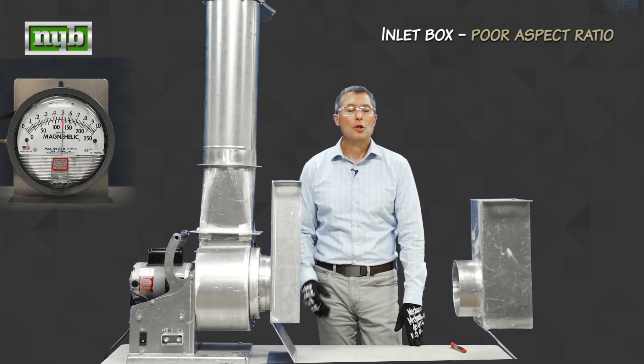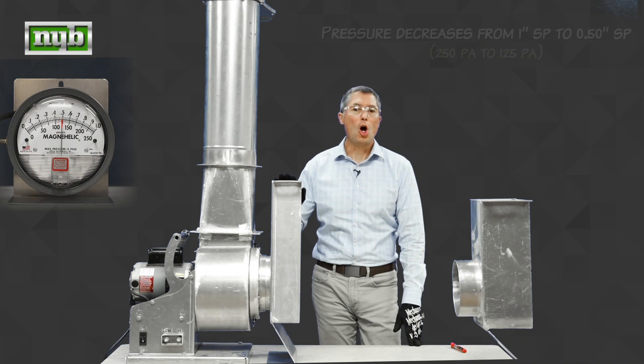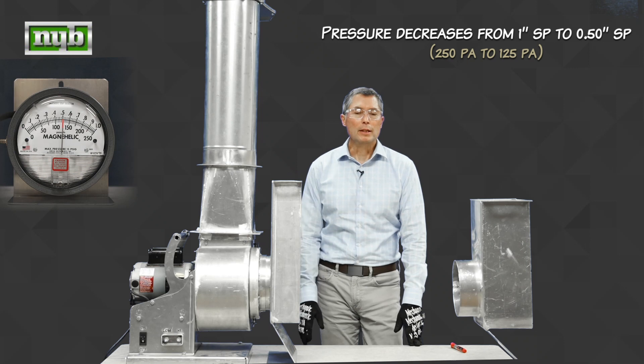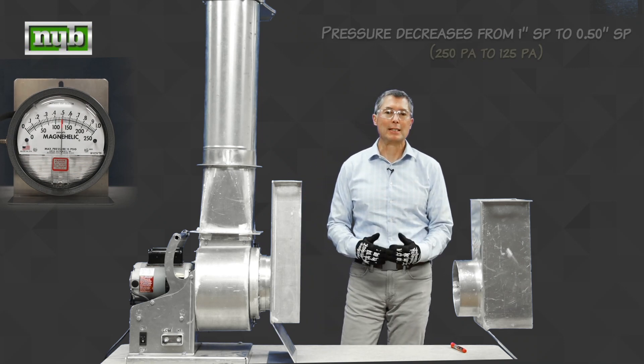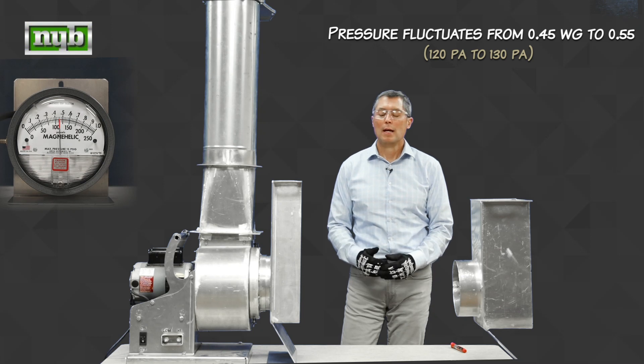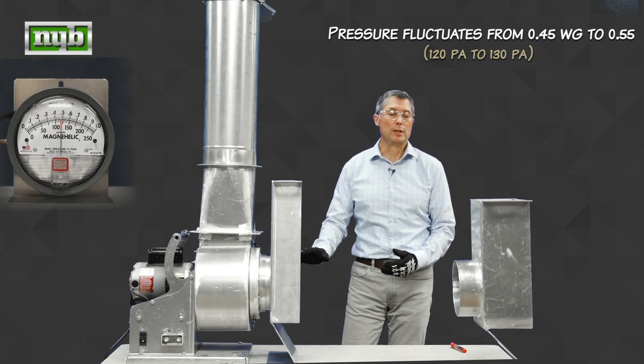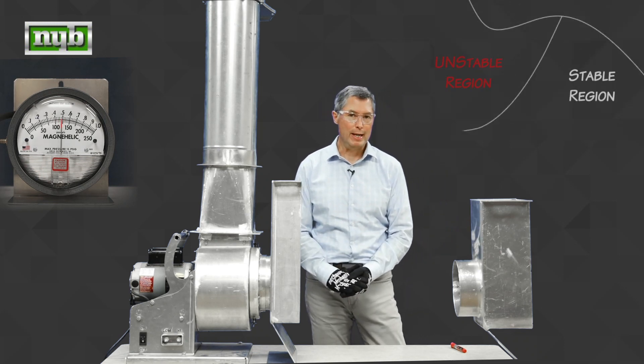Looking at the Magnehelic gauge, you'll notice a couple things. One is, it's a pretty substantial loss when we put this box onto the fan. Secondly, you'll notice that the needle on the Magnehelic is bouncing up and down. It's not at a steady state. That means that we've created turbulent flow with this fan. We've actually pushed this fan into an unstable region on the fan curve.